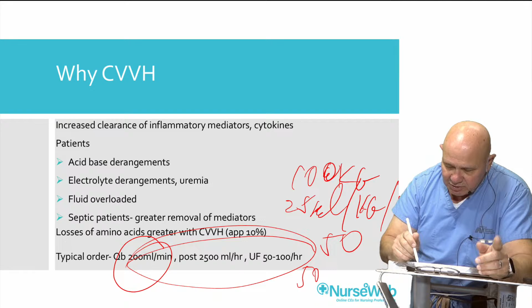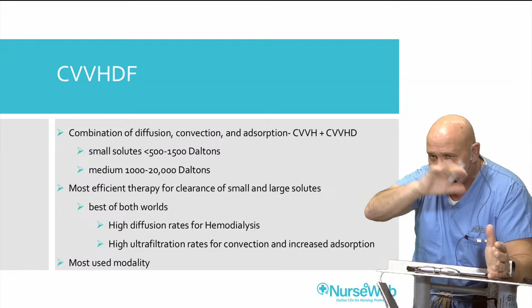What is the patient's weight? You have to know the patient's weight in order to prescribe CRRT in the correct way for milliliters per kilogram per hour. So keep that in mind. CVVHDF is just a more intensive therapy. It's where you're using every single pump. You've got the blood pump, you've got all the fluid pumps going, and CVVHDF is continuous veno-venous hemodiafiltration. So you're doing convective and diffusive clearance both at the same time, and it gives you the opportunity to replace more plasma water because you're using all of the pumps to help you be able to do that.